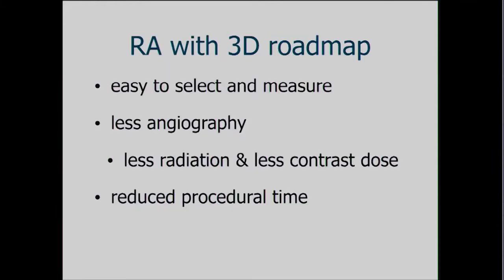The advantages of rotational angiography with 3D roadmap are: easy vessel selection and measurement, less angiography — meaning less radiation and less contrast dose — and reduced procedural time.